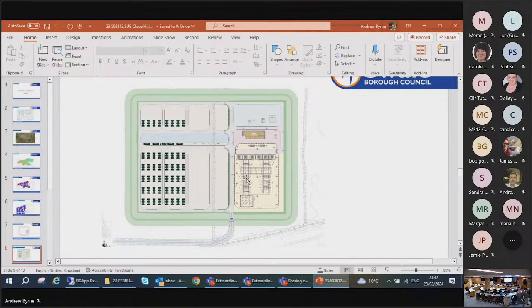The aerosol system is there for a fire in that wiring. It's PCS integrated with the battery management, and we've got gas detection, smoke detection, and heat detection. You do not want an aerosol discharge because that can create explosive conditions. So if there's a thermal runaway, the gas exhaust system operates to exhaust the explosive gases out. For wiring in the battery energy storage system, aerosol systems have demonstrated they're able to extinguish any electrical incident within those battery containers.